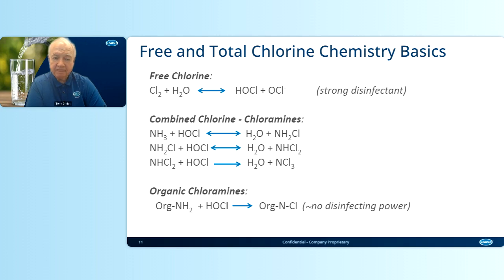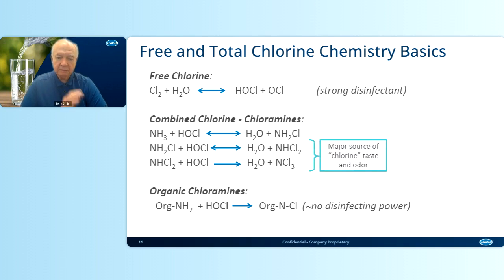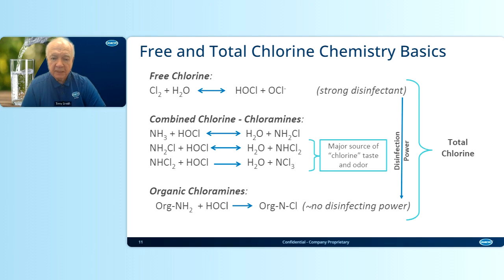Combined chlorine, or chloramines, are sometimes made on purpose, where we're making monochloramine for surface water systems. And then we can also have issues where we're not putting in the right amount of chlorine and ammonia and get dichloramines or trichloramines. And then we also have organic chloramines, which have no disinfecting value at all. So dichloramines and trichloramines are a major source of taste and odor. As I always say, the dichloramines taste bad and the trichloramines stink. And we also have less disinfecting power going from free chlorine down to chlororganics, which have no disinfecting power. But all of this is considered total chlorine.